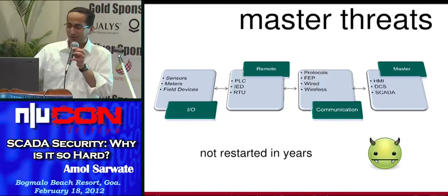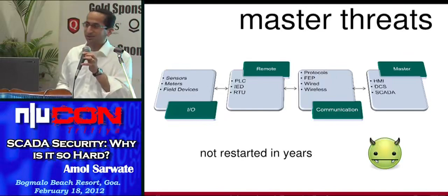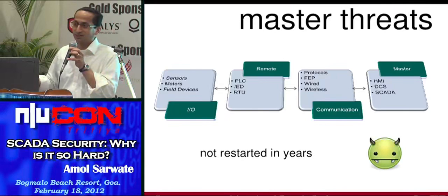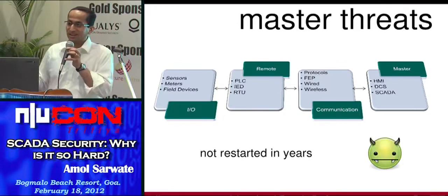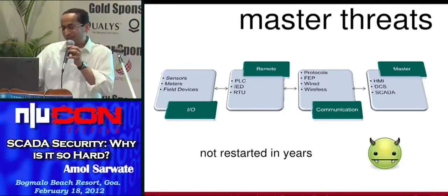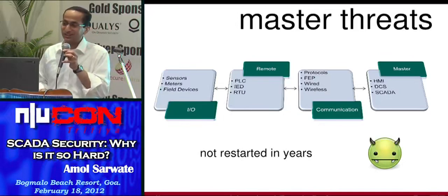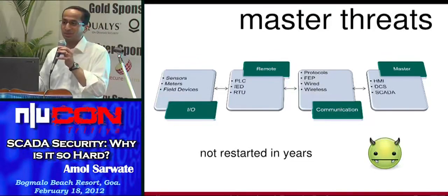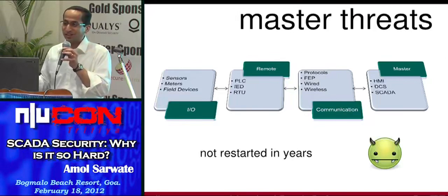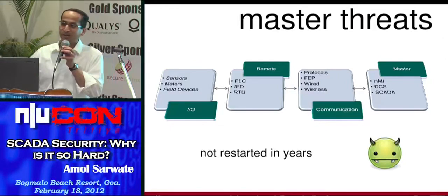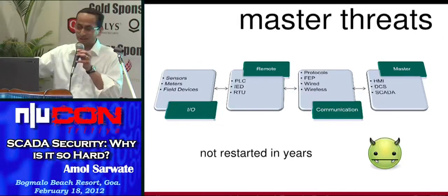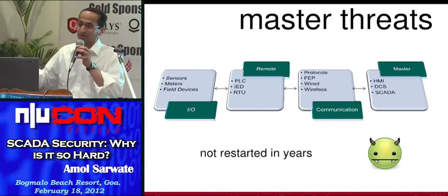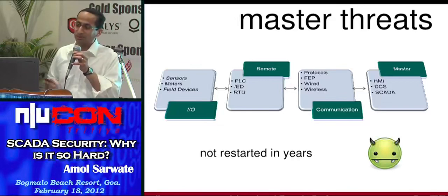And when we asked the fellows, they were very straightforward. They said they are not confident that the system will boot again if they reboot it. So we had a chuckle there, but it's actually a very serious thing that you have a SCADA system, such a critical infrastructure system, running an outdated operating system, not being patched, and not being restarted because there is a fear that it won't come back again. To circumvent that, there are a lot of battery backups and other things around that system just to keep it running.